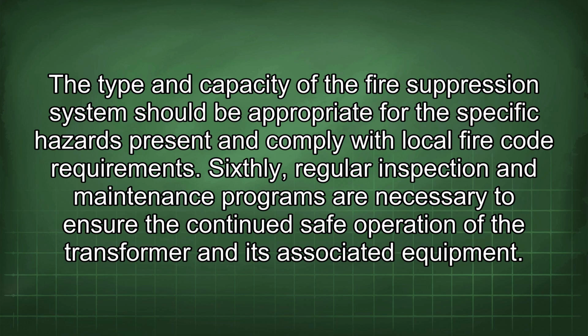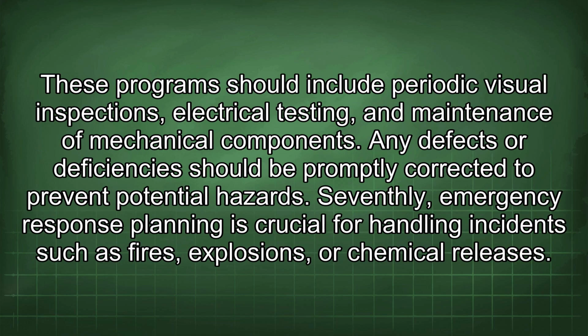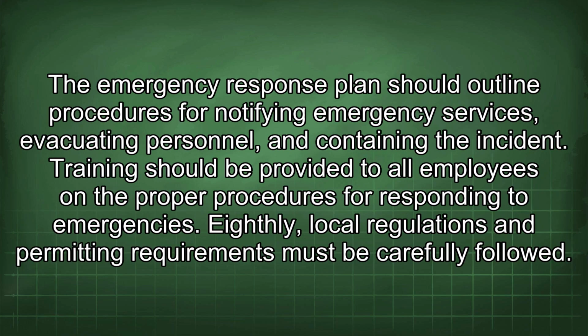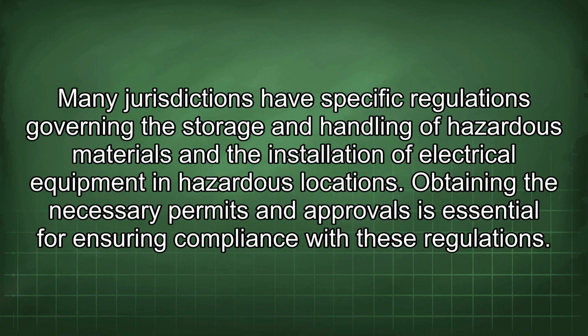Sixthly, regular inspection and maintenance programs are necessary to ensure the continued safe operation of the transformer and its associated equipment. These programs should include periodic visual inspections, electrical testing, and maintenance of mechanical components. Any defects or deficiencies should be promptly corrected to prevent potential hazards. Seventhly, emergency response planning is crucial for handling incidents such as fires, explosions, or chemical releases. The emergency response plan should outline procedures for notifying emergency services, evacuating personnel, and containing the incident. Training should be provided to all employees in the proper procedures for responding to emergencies. Eighthly, local regulations and permitting requirements must be carefully followed. Many jurisdictions have specific regulations governing the storage and handling of hazardous materials and the installation of electrical equipment in hazardous locations.